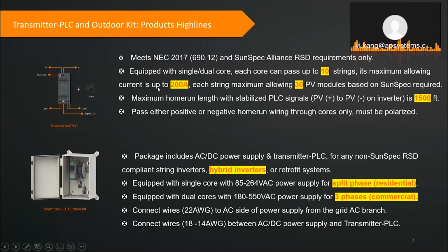That depends on the maximum allowable current that can go through that CT. Right now, we can reach up to 200 amp total. Some large jobs, especially commercial jobs, put more than 10 strings into a single core. There is also a risk, but as long as they are below these limitations, it will be fine. For residential, normally you will get only a single core with the package. Just letting you know that.